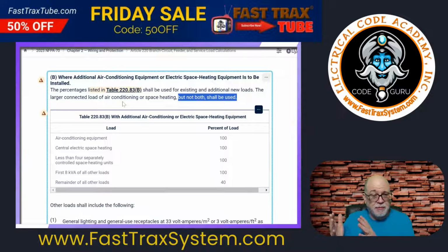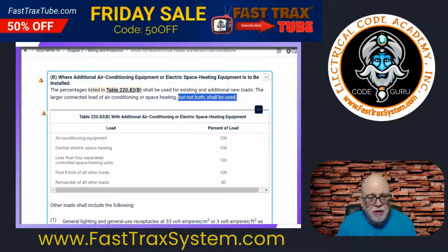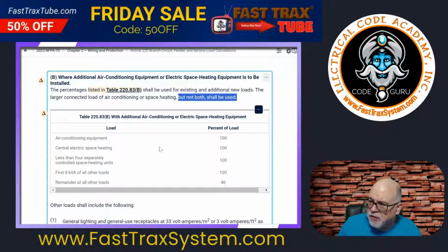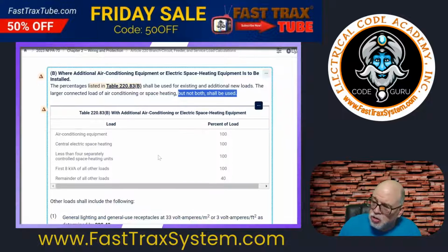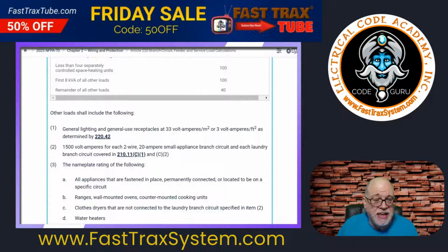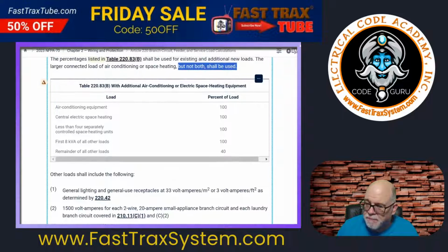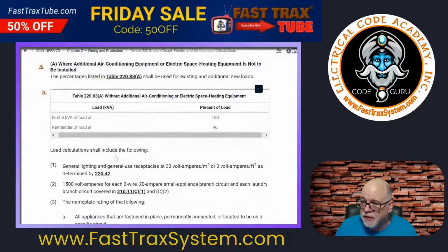Does that seem pretty similar? Right, so that's kind of the same way we do what? When we're doing the optional method where we look for the larger, the heat or the AC, that type of scenario. Same scenario here. Easy thing to remember is heating or air conditioning, they're all just taken at 100%, and whichever's larger, that's the one you take. And you add that to the calculation that you did similar to what we just did in A. There's no difference. It's just now you're adding the additional loads for B, okay? So that's all you're really doing there.